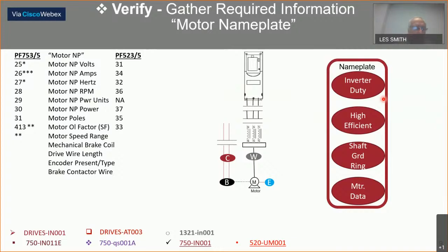Encoder present or not, and the brake contactor wire. And as you see over here to the right, the brake contactor here, the wire, there's the contactor, and here's the brake itself. You treat this differently than you do these over here. This is the drive wire. There's the encoder. Again, just using that diagram to help get a picture in your mind.